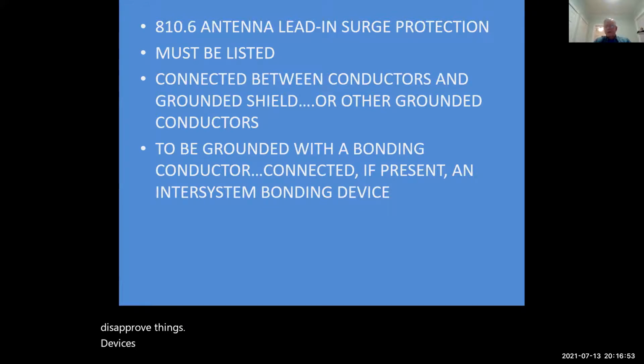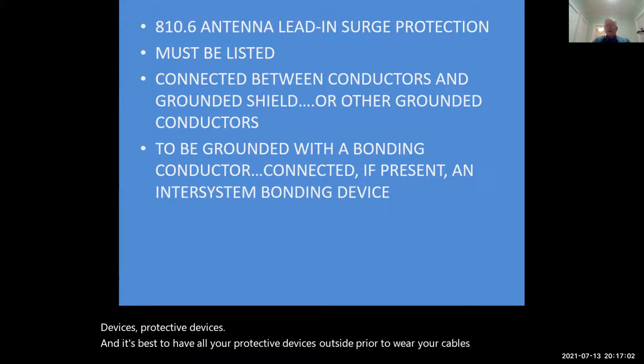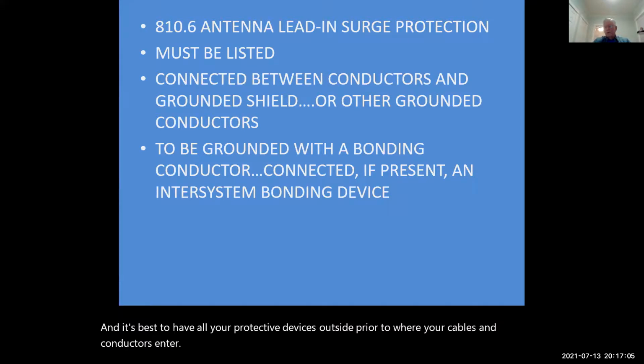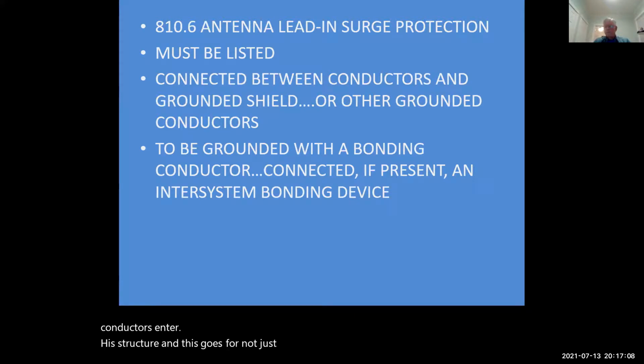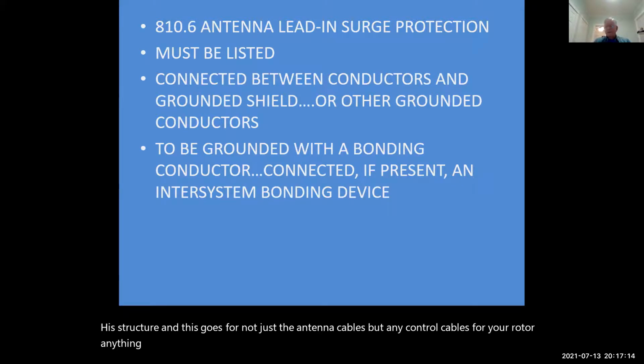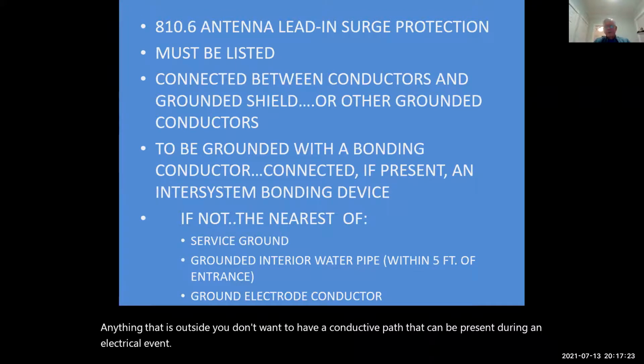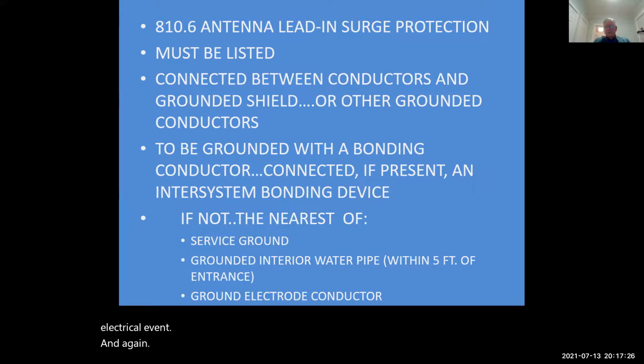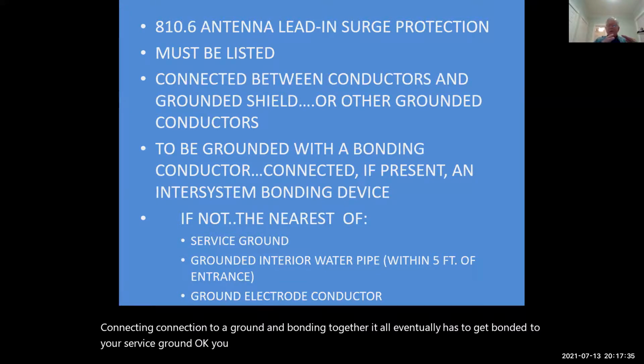Protective devices: it's best to have all your protective devices outside, prior to where your cables and conductors enter your structure. And this goes not just for the antenna cables, but for any control cables for your rotor, anything that is outside. You don't want to have a conductive path that can be present during an electrical event. And again, connection to a ground and bonding together, it all eventually has to get bonded to your service ground. You want everything all bonded together.